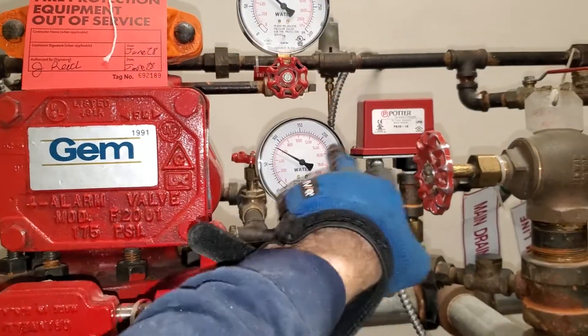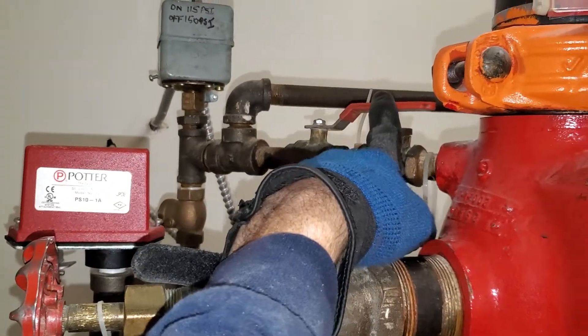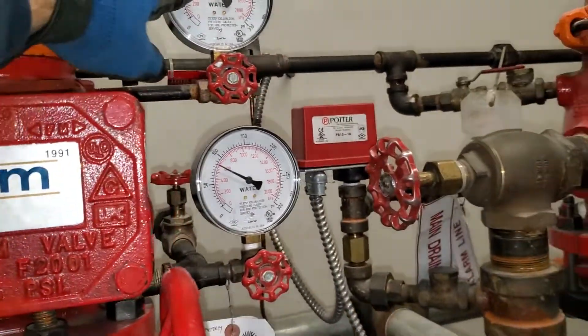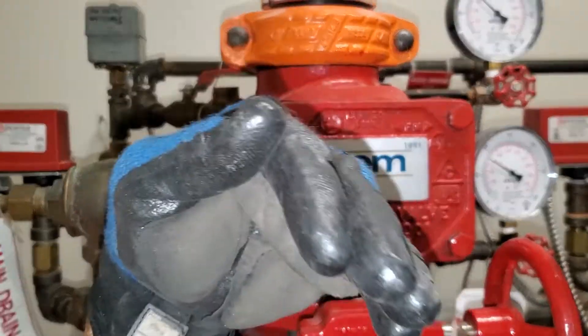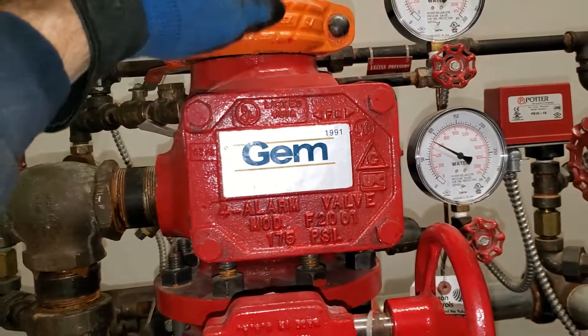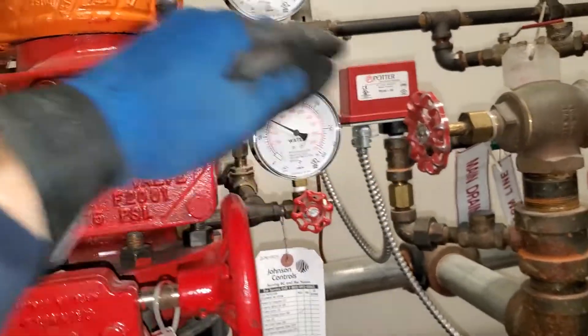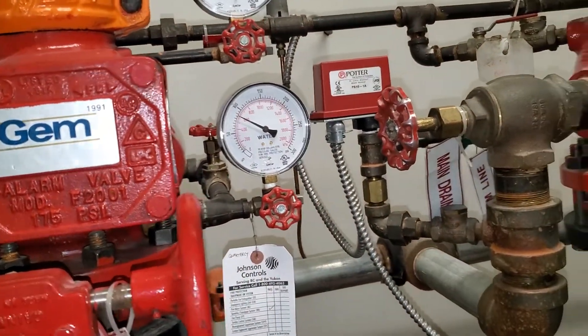The pressure is built up, so what I did was I reopened the excess pressure line — the excess pressure pump — and now there's building pressure on top more than the bottom. So inside of this there's a check valve, and it closes, and the pressure on top pushes down, so there's more pressure on top than there is on the bottom.